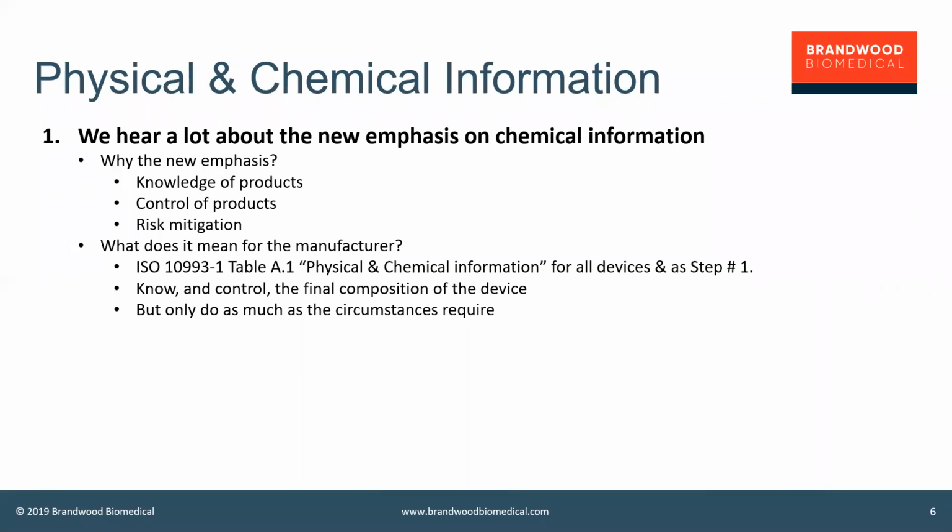And that, of course, will involve the judgment of the manufacturers and a rationale for why a particular approach was taken. And of course, every rationale needs to be written down so that it's accessible to regulators and notified bodies and anybody else who's an interested player. So this is about knowing, saying what you know, and saying why you think that's okay.